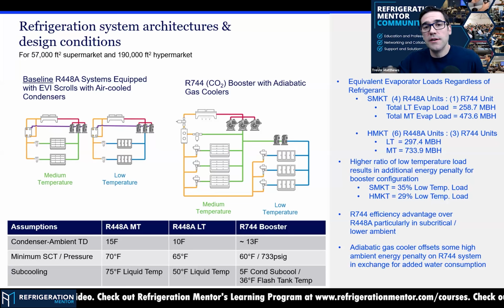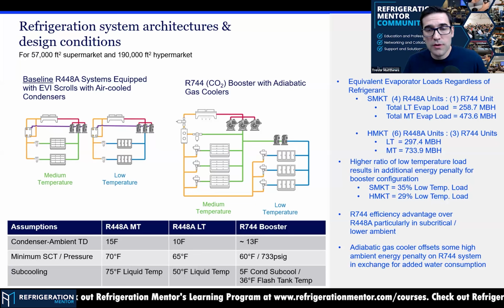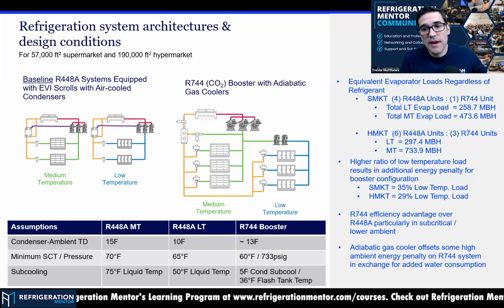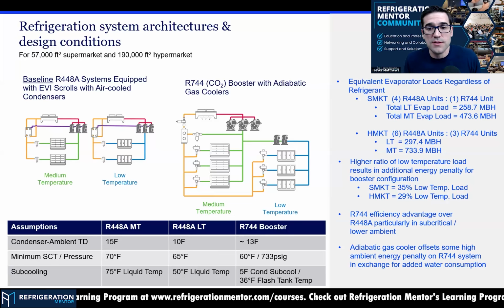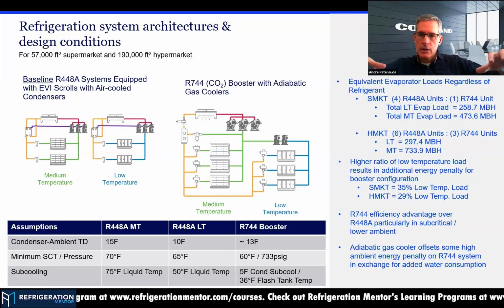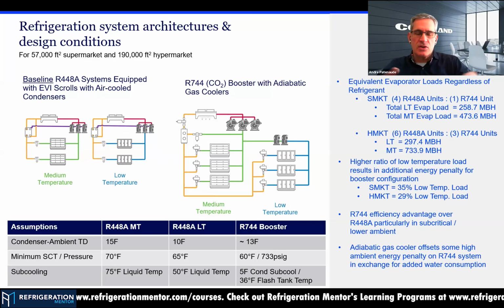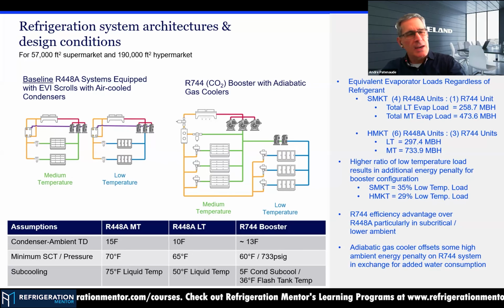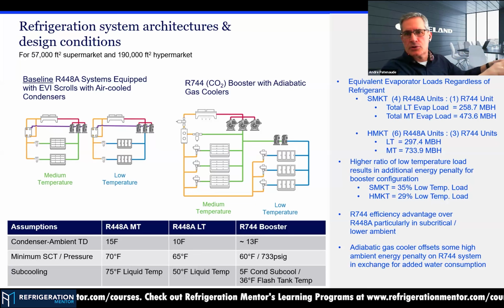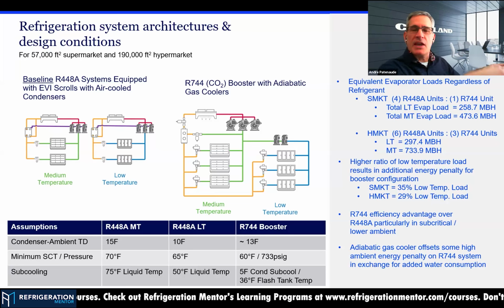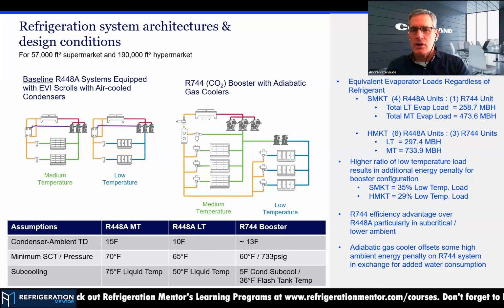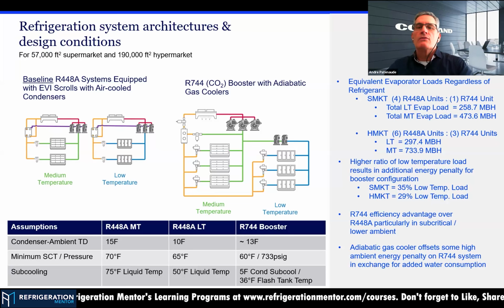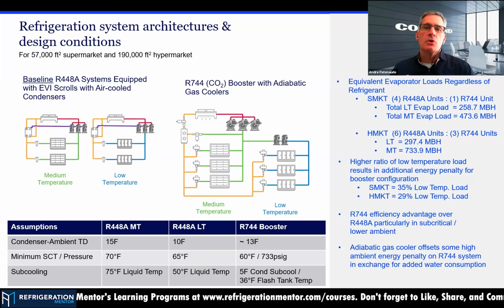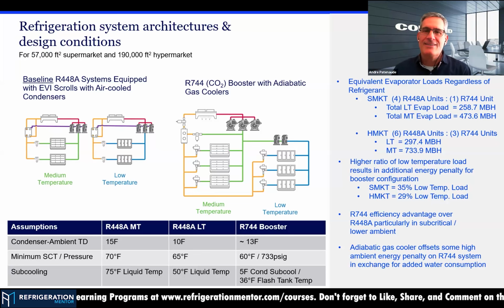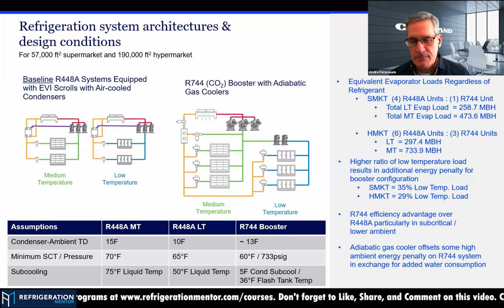But it's something that you want to understand, because the more load that you got to come there is going to affect what happens on the medium temp side, and then that all goes back to an amount of energy that that unit uses. No, you're right. So conceptually, you may have a service tech that has access to energy numbers in one store. And it might look like the same footprint as another store down the street, but the energy might be higher because that store has more low temp load to total. Exactly. So understanding that, you may go, now I get it. Now it makes sense why it's a little bit higher.